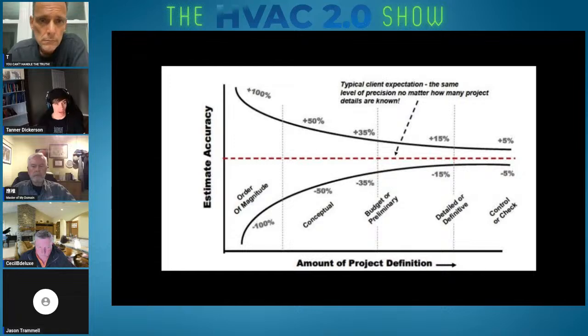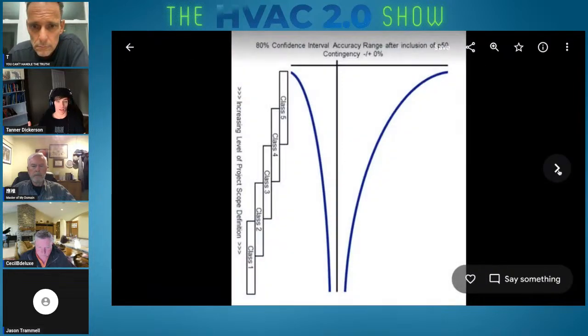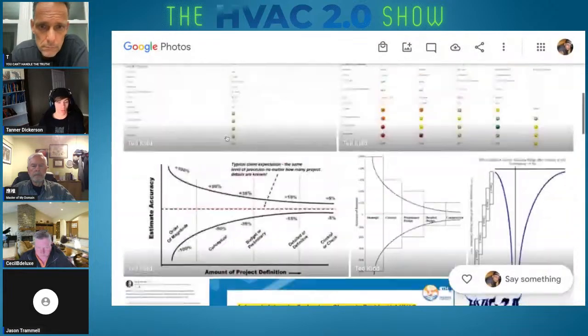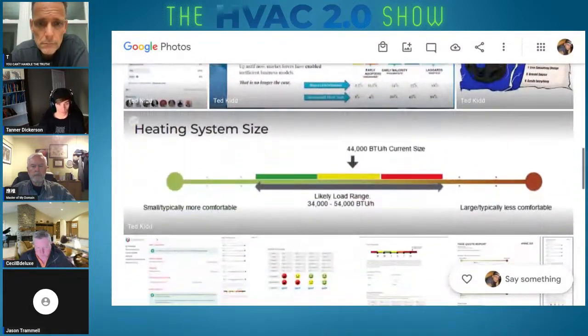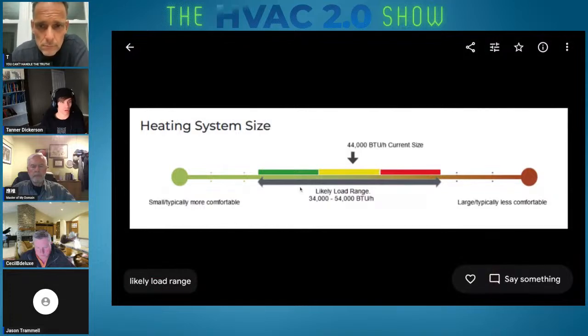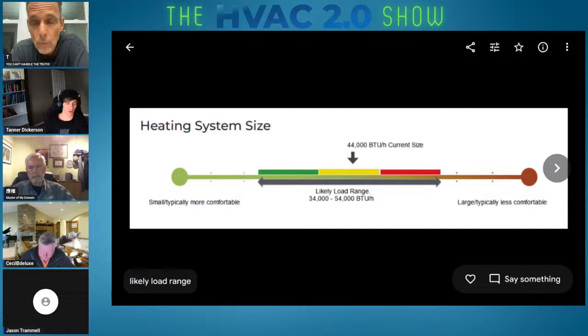It's nothing but an educated guess, and we're just putting this educated guess into a more visual, friendly method. So when somebody's looking at this, they can go, okay, without the unknown variable of leakage that we don't know, here's where it could potentially fall. If we're not going to pay to do the blower door test, we have to decide: do I have a good house, a mediocre house, or a poor house relative to other houses of the same size? Do I want to oversize my equipment to what a good house looks like, and oversize it potentially to the ductwork I've got?